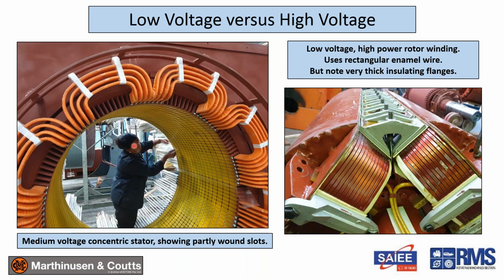Partly wound concentric stator, quite rare. You can see the open slots there that haven't been wound yet, and these coils have been fitted with wedges added. Another example of a wound field using rectangular conductor. Again here, notice the thickness of the insulation separating the whole field, and this is actually quite a thin design. It's an alternator, which they tend to push limits on, even historically.